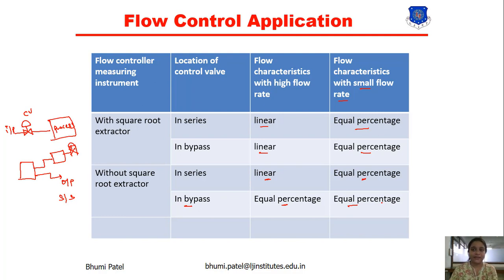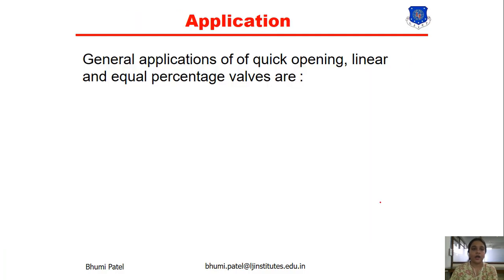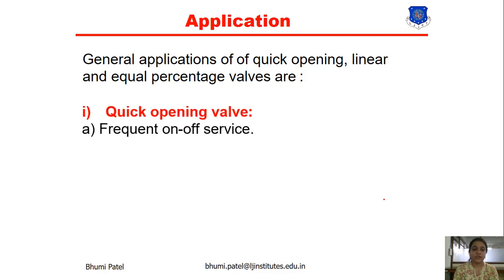This is the summary of the flow control application for the control valve. For the general application of quick opening, linear, and equal percentage valves — the first application of quick opening is for frequent on-off service. Whenever on or off service is required, we use the quick opening valve because we can get a quick output at the instant of the input.